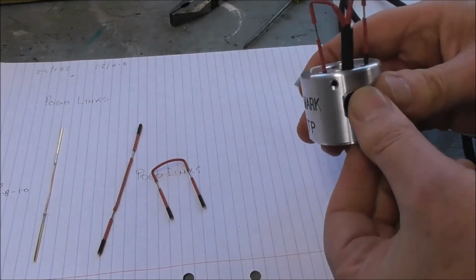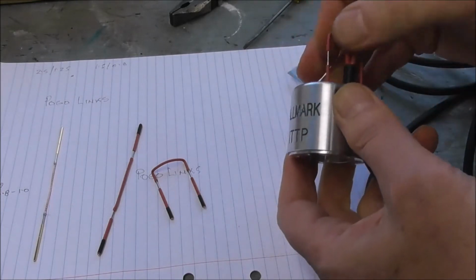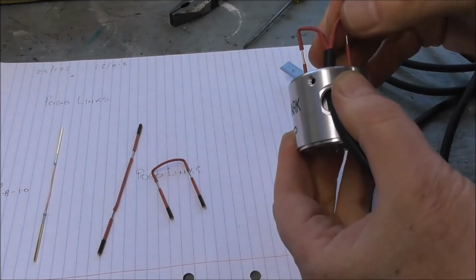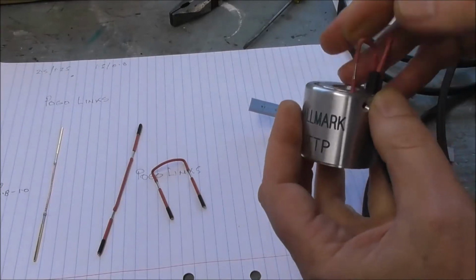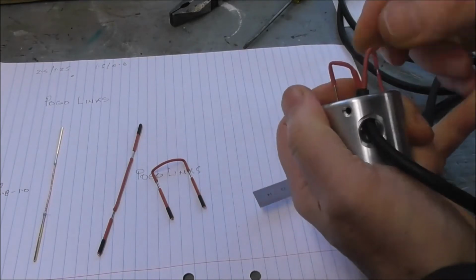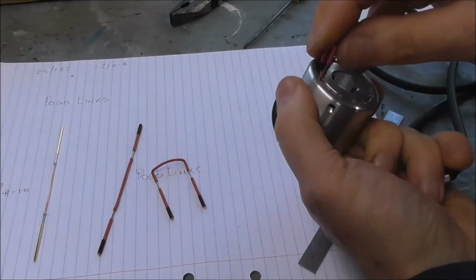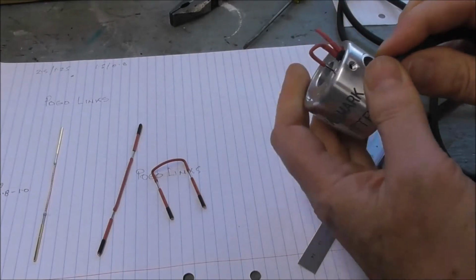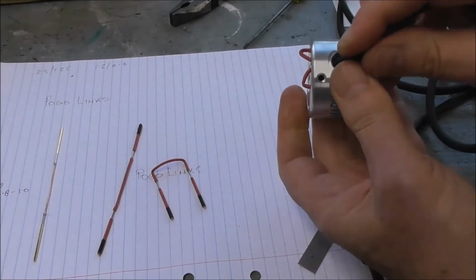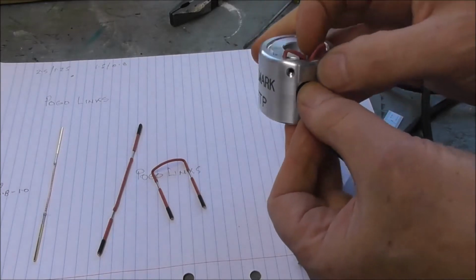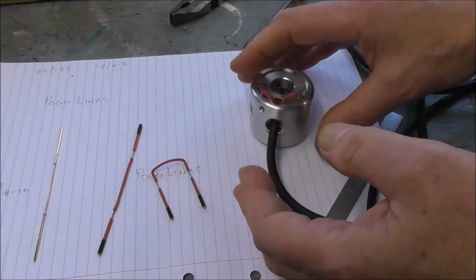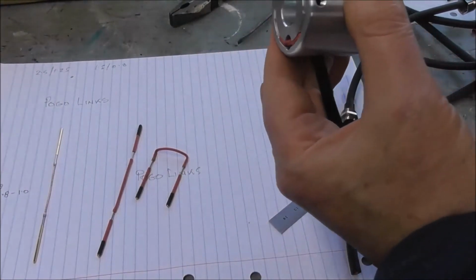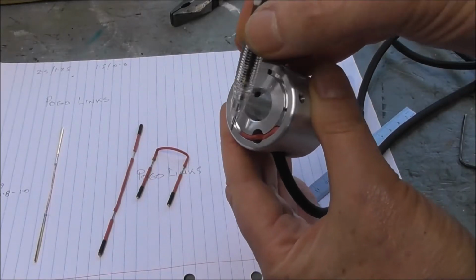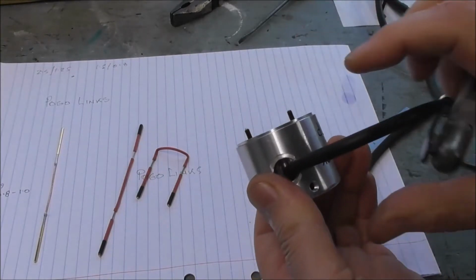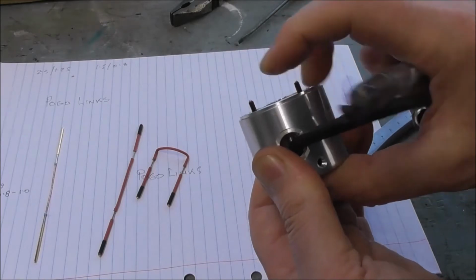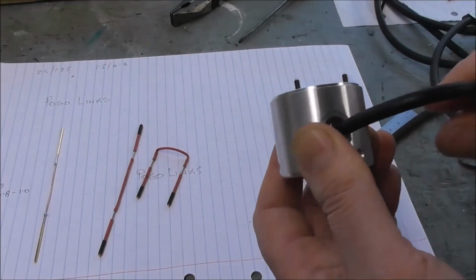entering the pogos into the adjacent holes there and pulling the main cable down and just gently feeding it in. Don't use any force. It has to enter without any force. And if it's not going in smoothly, it's because something is snagged, and you just need to be a bit careful to ease it in. And then finally, I'll probably need to concentrate just getting everything in line, pulling it down gently, and I'll get back to you in a sec. Okay, we've got the wires right in now. The pogos are standing out like that. Check that they spring in and out freely. If they stick in, there's something wrong.